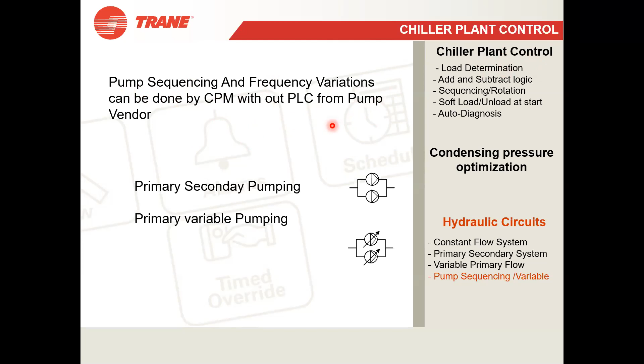Now, summarizing, you can answer yourself. Plant load determination effectively: can your building BMS do it? No, the building BMS will not be able to do it. Custom sequences on the chiller: this is not possible, because the building BMS can only see or provide the data and can only switch on or switch off, but it cannot modulate or regulate anything. So all these features will not be possible using the building BMS.